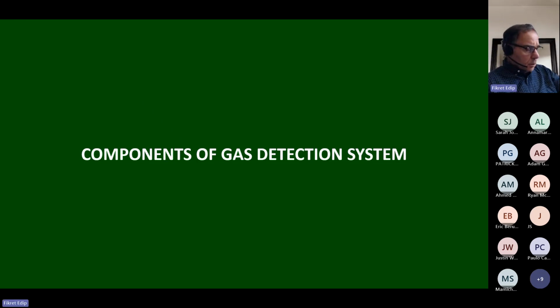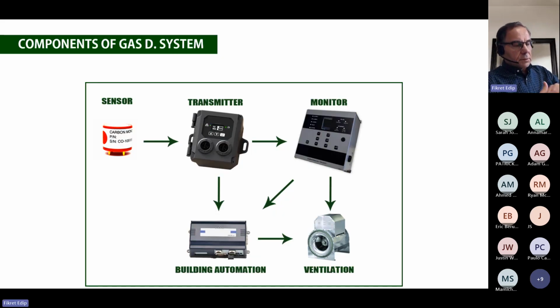Okay. The components of a gas detection system start from the sensor element. The sensor element is put inside a box, a unit with a circuit board and all that. The signal coming out of the sensor gets amplified in multiple levels so that the transmitter now takes that signal, translates it to an analog or digital signal, and sends it to the controller. The controller takes care of the ventilation system and at the same time sends a signal to the building automation system. The building automation system can start the ventilation also.